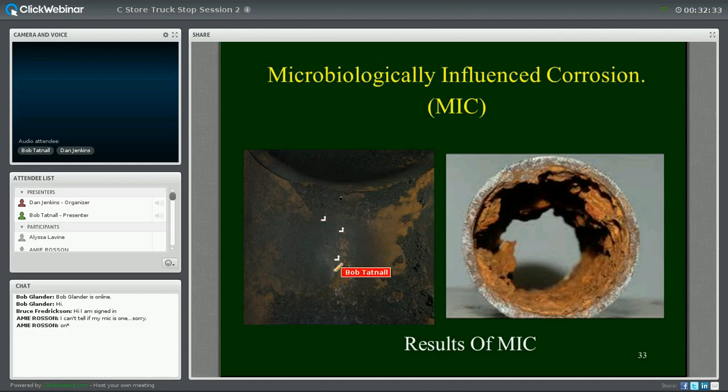In the bottom area where water collected first and sludge grew, we get pitting corrosion and we get penetration, and some people are promoting the use of ultrasonic calipers to check tanks for thickness. That works in the industrial world. In home heating oil tanks, it doesn't usually work because, as I said, the ultrasonic gauge is going to say this tank has full thickness, and you could not measure where there's a pit. You wouldn't get an indication, so it's invisible to those sorts of instruments.